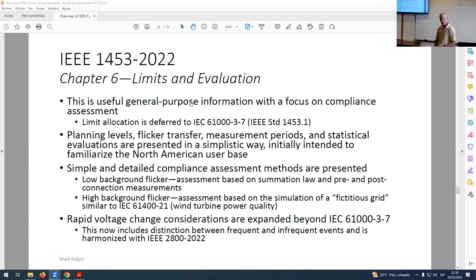So how do you assess whether or not a particular customer complies with the limit that you gave? You can't measure that. What are you going to do? Well, there's a couple of options that are given in 1453. And they're broken down based on whether the existing background flicker is low or high. If it's a low level of background flicker, then it is recommended, meaning it would be okay, if you simply use the summation law to separate the pre-connection flicker from the post-connection flicker. And in so doing, you can identify the contribution of the individual user. That only works if the existing background flicker level is low. If the background flicker level is high, what do you do then?